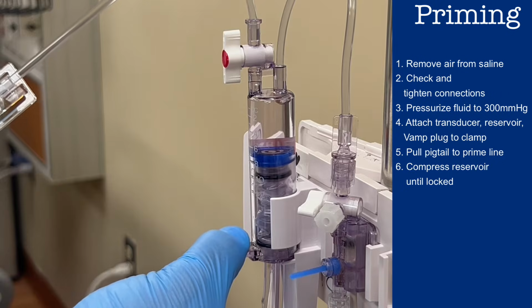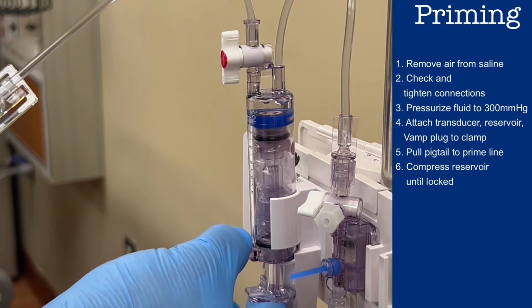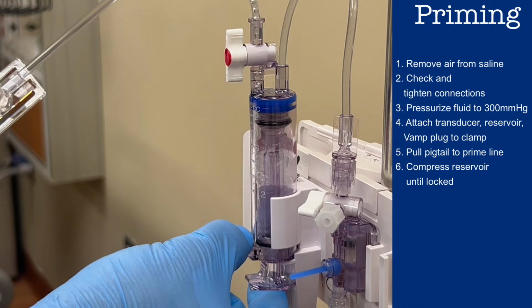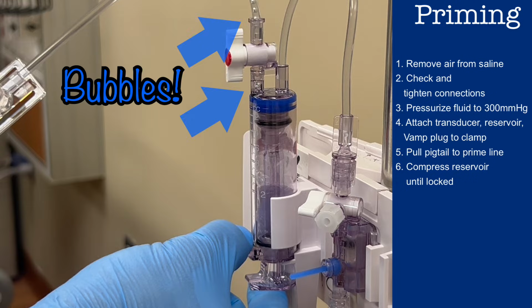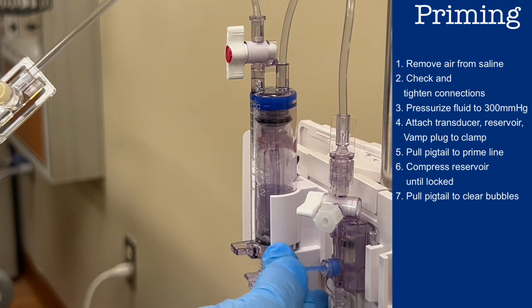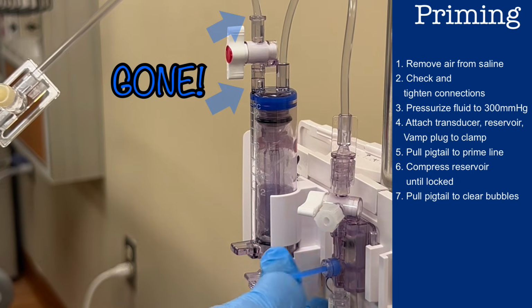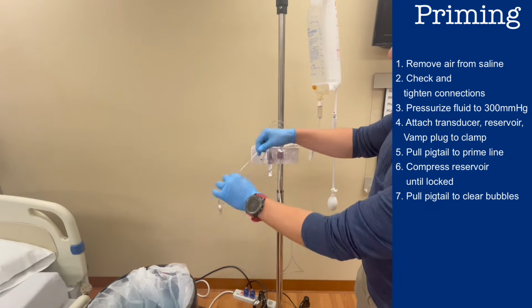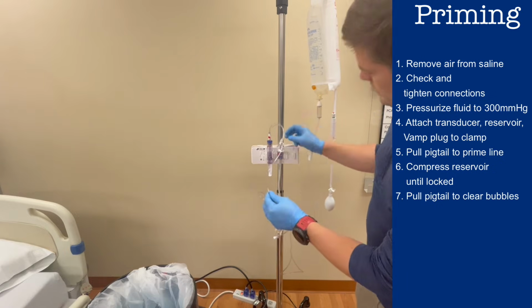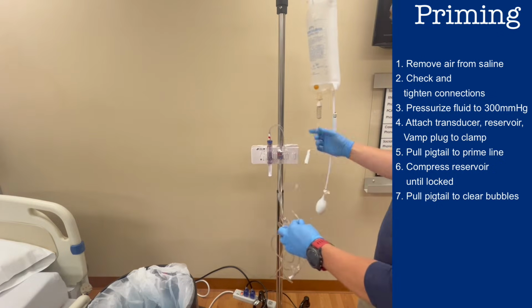Push the plunger up until you hear and feel the plunger lock click into place. Fluid will continue to squirt out of the end of the tubing while you do this. Then, to ensure that there are not small air bubbles still in the reservoir, pull the pigtail for a few more seconds to clear them from the line. Now assess the tubing looking for any remaining air bubbles. Make sure you clear all bubbles before proceeding.